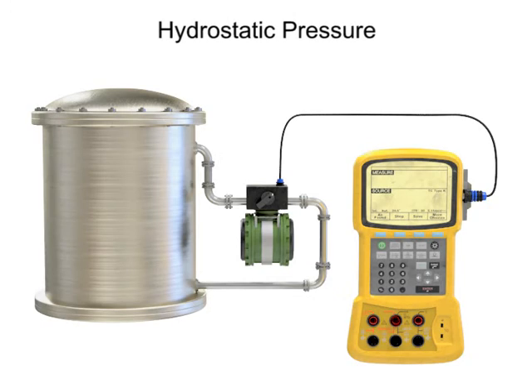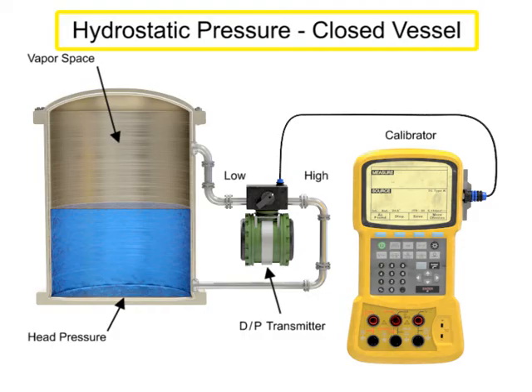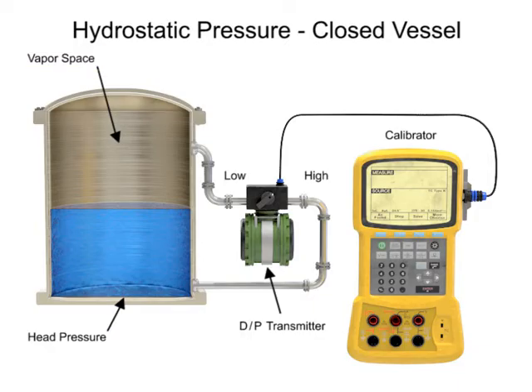Hydrostatic pressure can only be calculated from an open container. Within a closed or pressurized vessel, the vapor space above the column of material adds pressure and results in inaccurate calculated values. The vessel pressure can be compensated for by using a differential pressure transmitter.